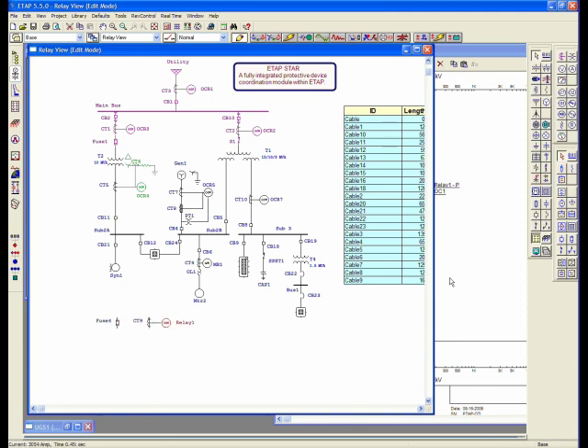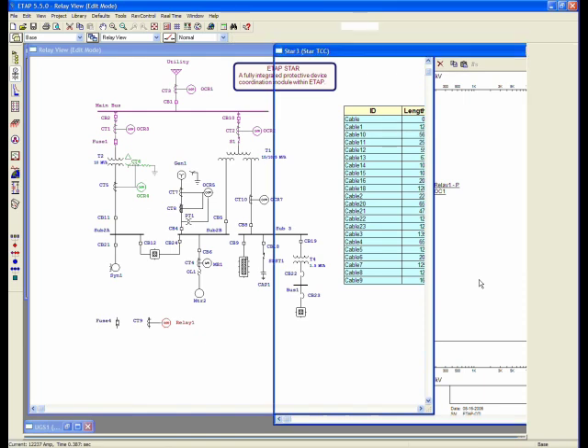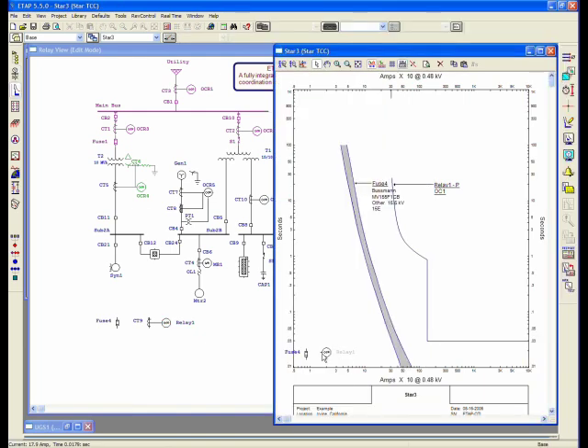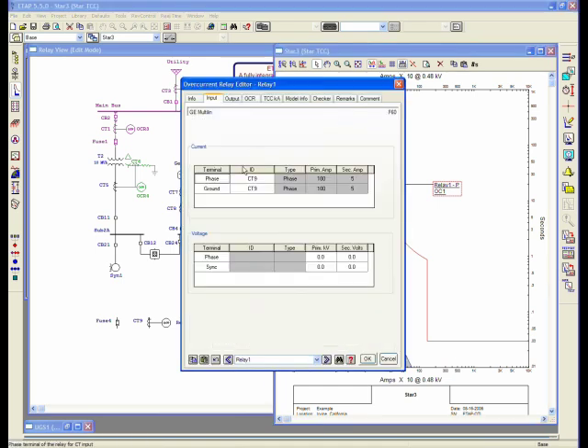So now I have a CT connected to this relay. I can drop the CT into here, or I can simply, since this element already knows it's connected to a CT, I can go into here and go to my input page, and it shows CT9 being connected to my phase and ground terminals, where it's shown as gray, and that means that basically that CT is externally connected.